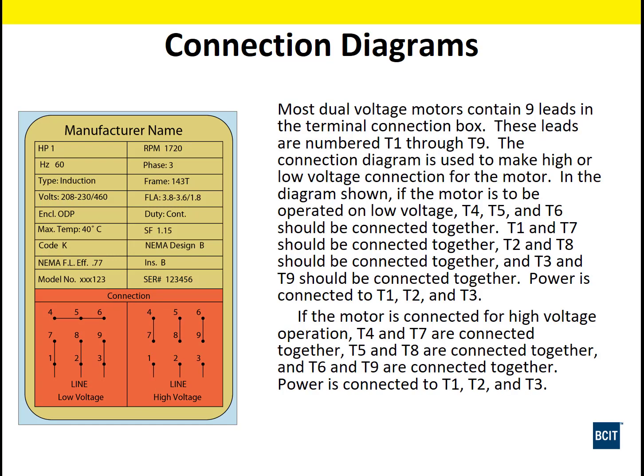Now here we have our connection diagrams. All right, because we have dual voltages on this motor, we're going to have 2 different types of connections. On the left here, we have our low voltage connection. On the right, we have our high voltage connection. Okay, and you guys remember, this is if this is a Y connected motor. I'll tell you a little secret here. If it's a 9 lead delta, typically this middle terminal and the 3, they're swapped. The actual middle terminal on a lot of the delta motors are 3 here and 3 on this side. So it's a little bit of a telltale sign to tell the difference, but technically, if you didn't know that, they could be either 9-lead delta or 9-lead Y.